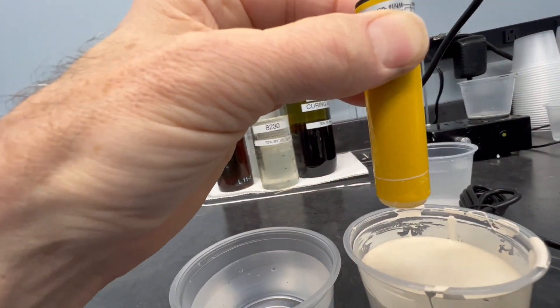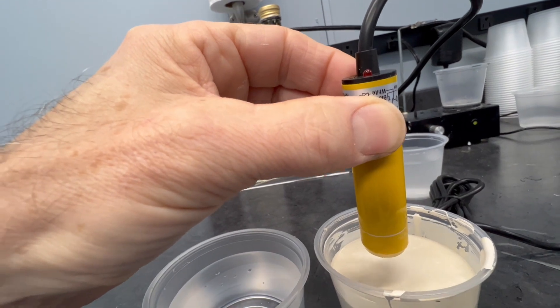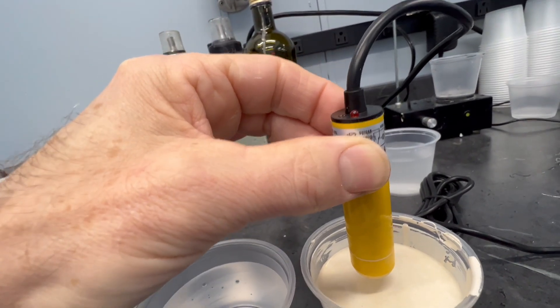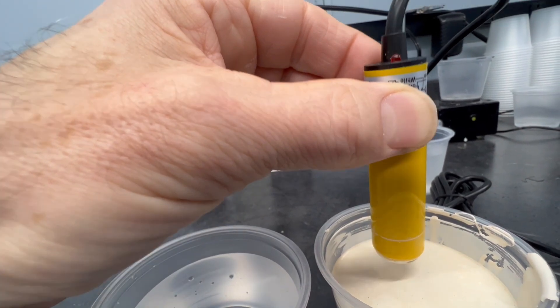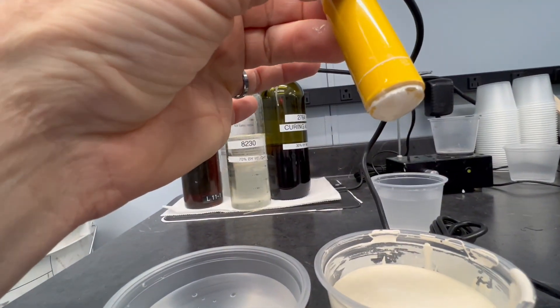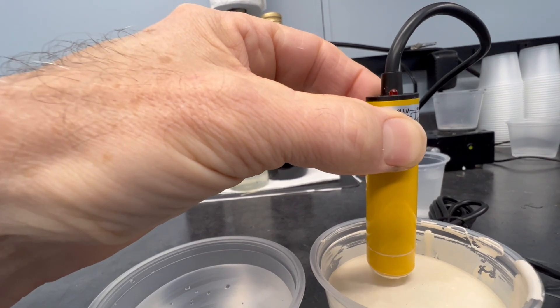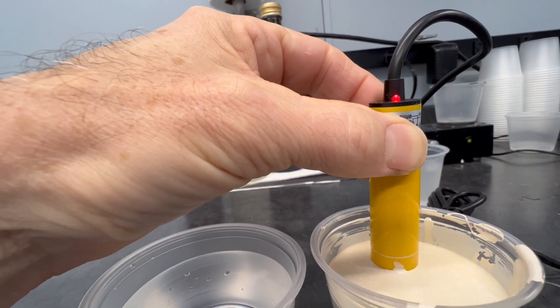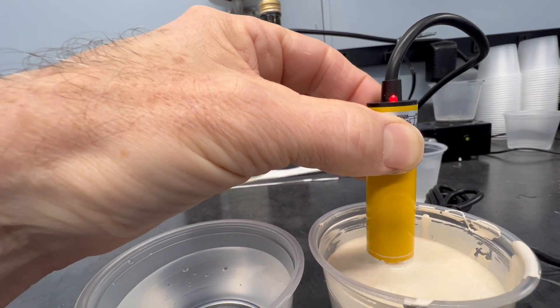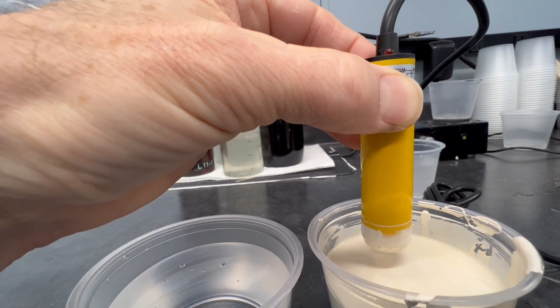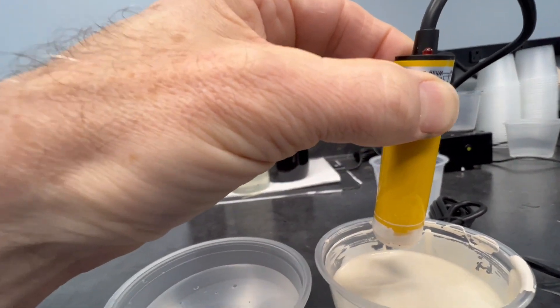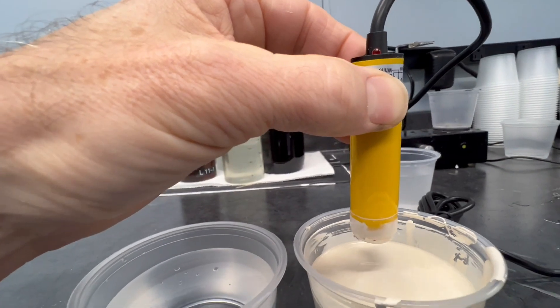So now we're going to go into some paint. Same thing. Let's see if we can catch this. So now it's just touching the paint. Just the bottom. I'm going to put it all the way into the paint now. And even though there's quite a bit of paint coating the surface, it still recognizes that it's no longer at high level.